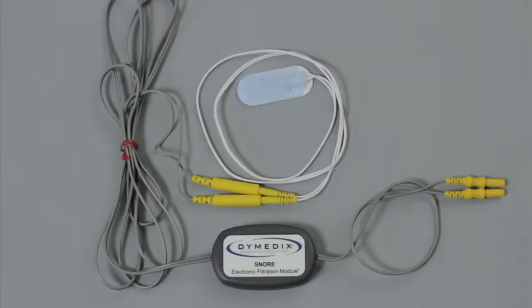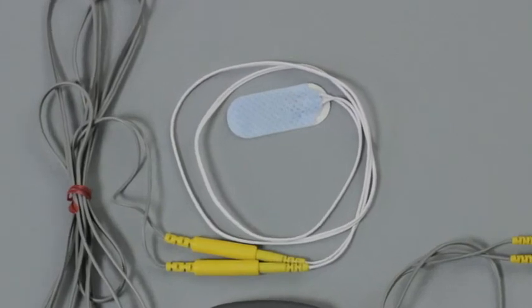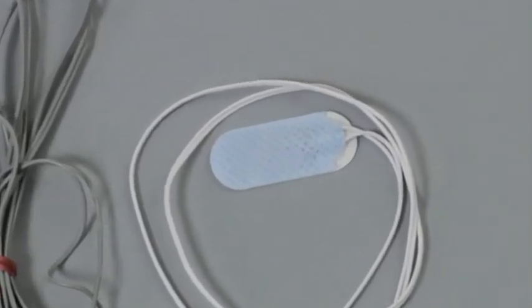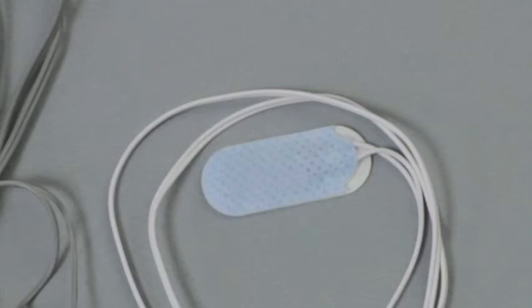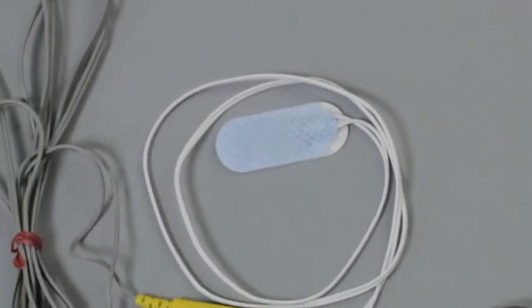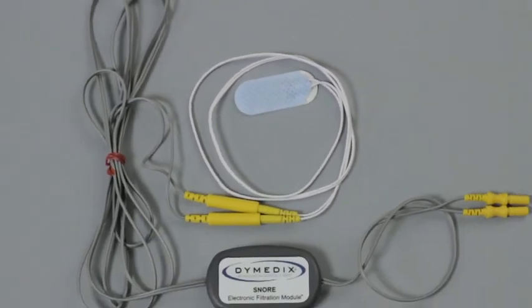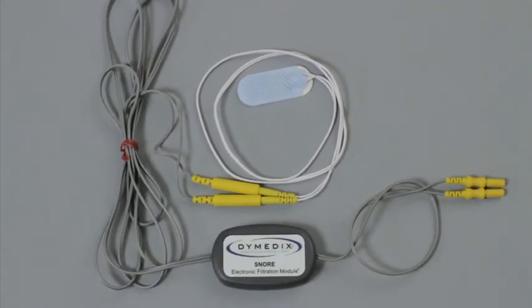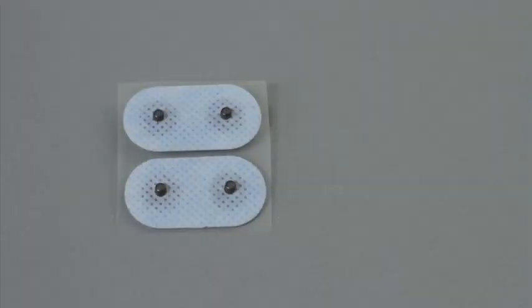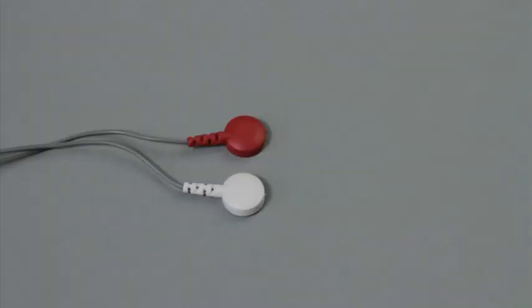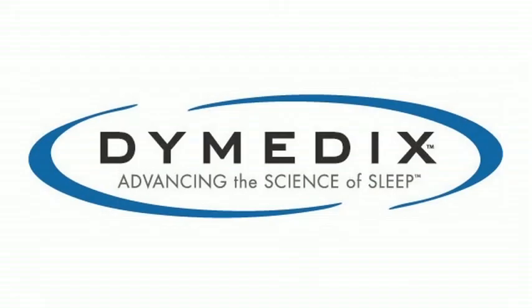PVDF can also be used to detect snoring. Because of its high sensitivity, the Dymedix snore sensor does not need to be on the sweet spot, thus avoiding carotid artifact. Setup is simple, and special noise reduction circuitry provides the cleanest baseline in the industry, allowing for the detection of subtle snore events. Dymedix also was the first to manufacture unique electrodes for the legs and the chin, along with snap electrode lead wires with high strength and durability. Better data starts with better sensors, and better sensors start with Dymedix.